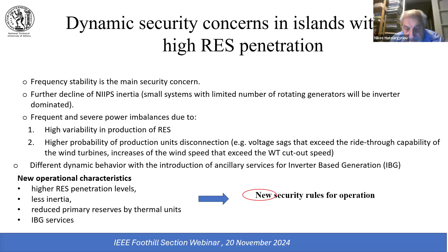And when I say new, I mean that already now you have current security rules that basically restrict the penetration of renewables. So renewables, especially wind farms, are subject to power limitations, first because they need to keep a number of thermal units in the system, so they have to respect the technical minima. There's a dynamic penetration level limit, which is applied for stability purposes. Basically, this is again a static rule of 20 or 35% of the total demand. Also, the primary reserve levels are specified according to each island's characteristics, but they are static levels, and they are normally conservative and do not guarantee the frequency stability, as you will see next.